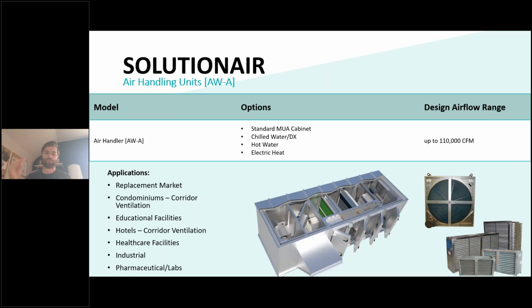But there are soft caps within that. So for wheels, for instance, we tend to cap out around 20 to 30,000 CFM, just based on the size of the wheel exceeding our factory's capabilities once you start getting above that point.